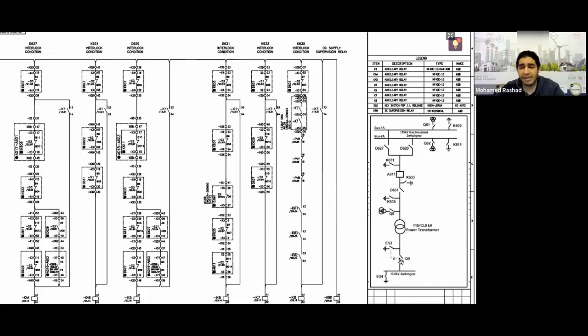Well, the breaker can be racked out, but still, when the breaker is racked out, there is also a lock. I don't want to go into details at first because it varies from one manufacturer to another. There is a lock to prevent the breaker from being inserted again as rack in. I also take this into account with the interlock. The breaker must be racked out and locked, meaning it is secured as racked out.